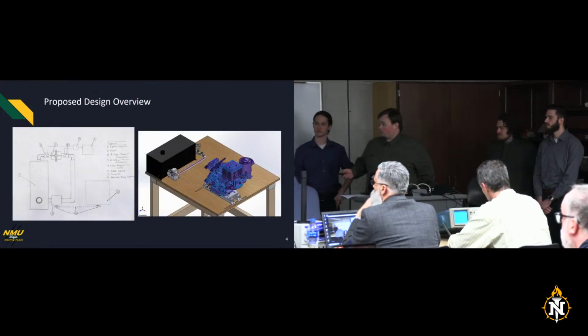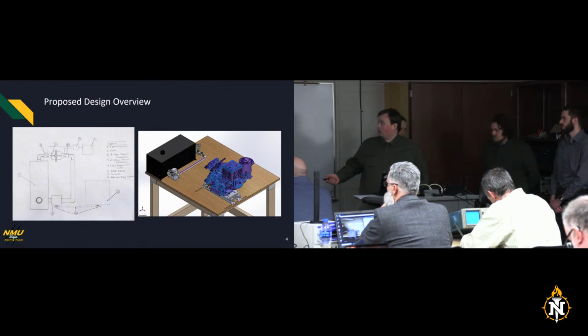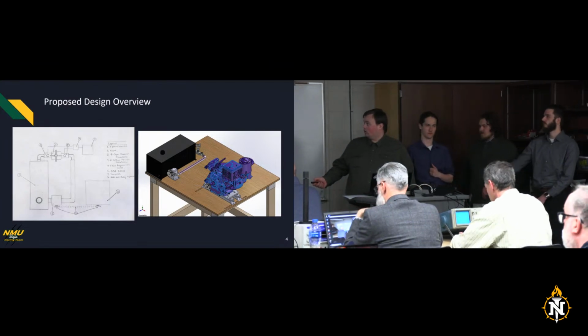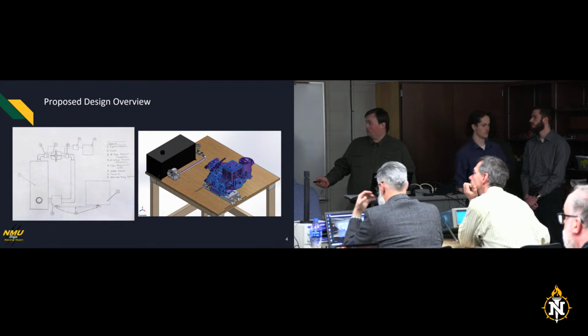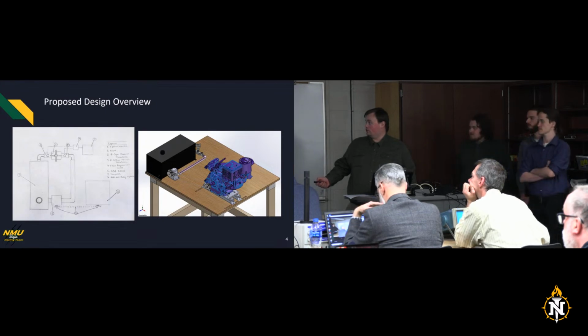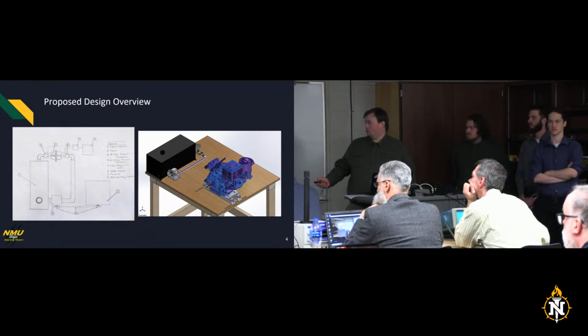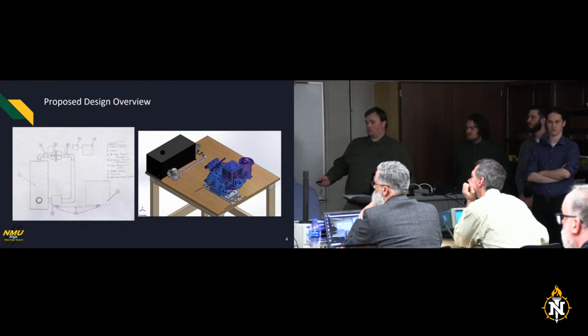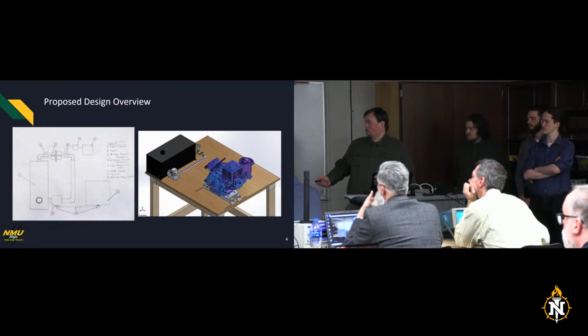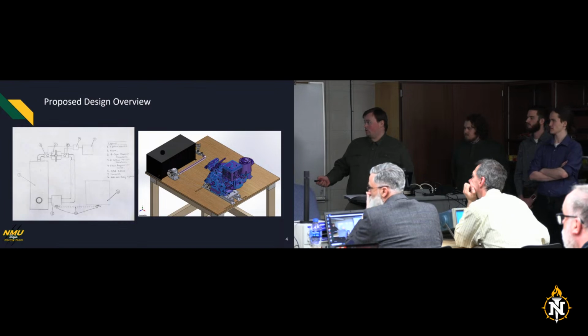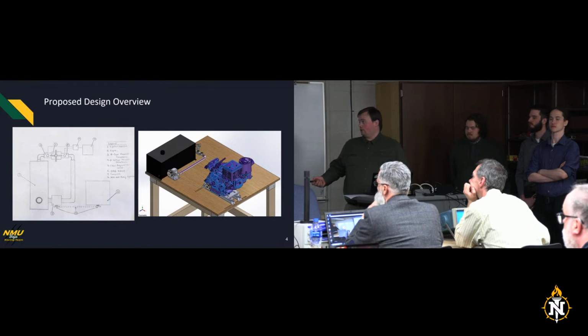This is our general design overview. Some of you have seen this before, but here's the engine to be tested, with the power and fluid loop. We have two pressure transducers and a throttling valve to increase or hit a targeted pressure in the system. By measuring that pressure and using the general energy equation for fluid flow, we're able to measure the power added to the fluid by the pump. Combining that with the mechanical efficiency of the pump, we can find the power required by the pump and therefore the load on the motor.